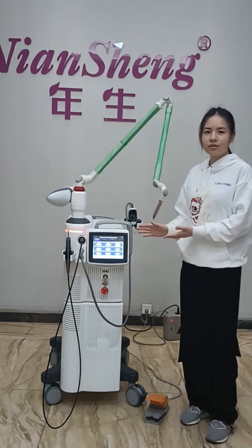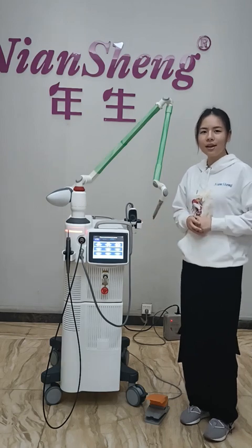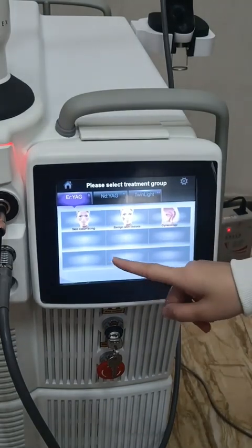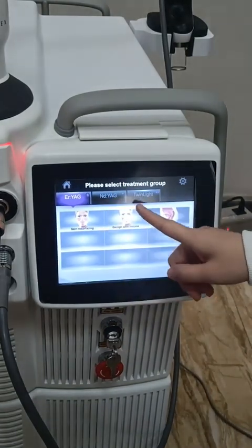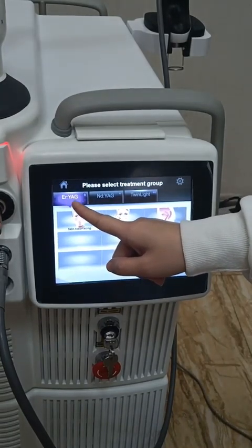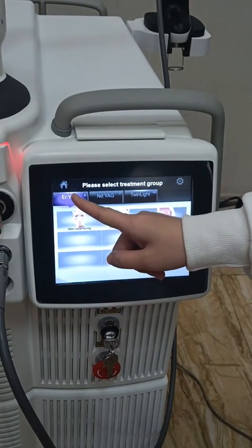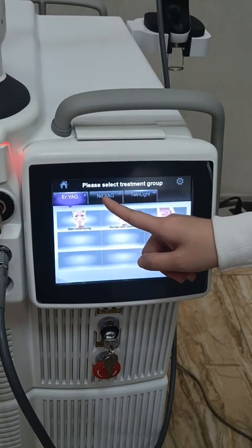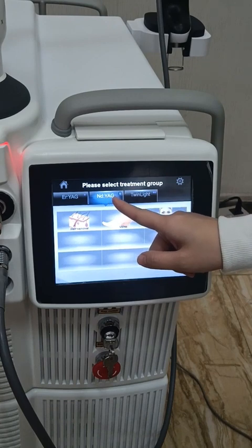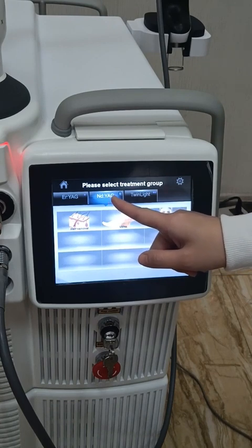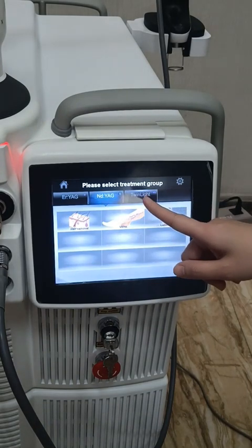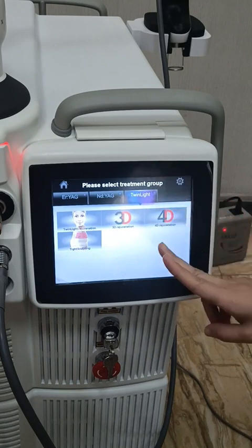Now I will introduce the functions one by one. We can see this is the main interface. There will be three treatment groups. The first one is the Er:YAG laser, which is the 2940nm wavelength. The second one is the Nd:YAG laser, which is the 1064nm wavelength. And the third one is the Twin Light, which is the combination of the two wavelengths.